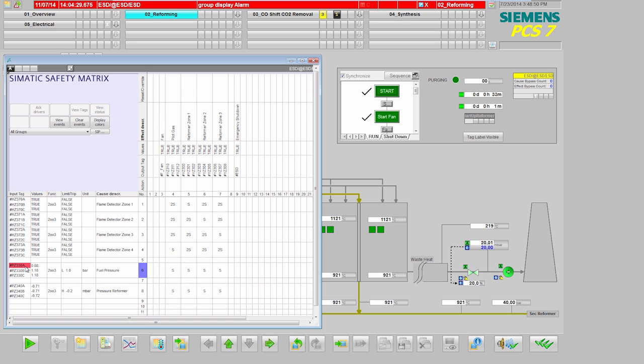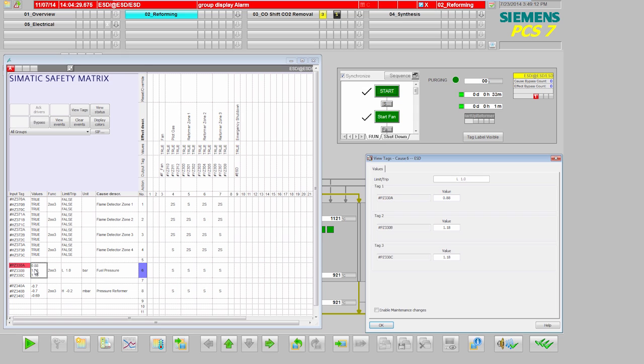In particular, for maintenance purposes, the safety matrix offers the option of a selective simulation of single measuring points, so that if the maintenance engineer will remove the wrong measuring point by mistake, the two of three requirement would not get activated.